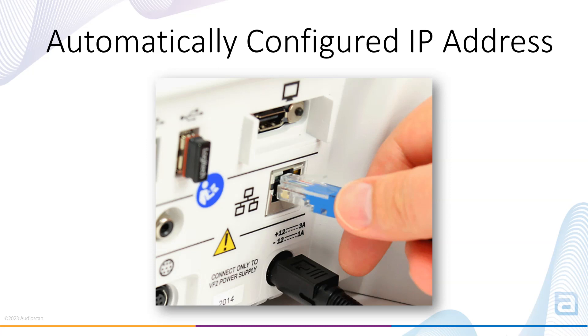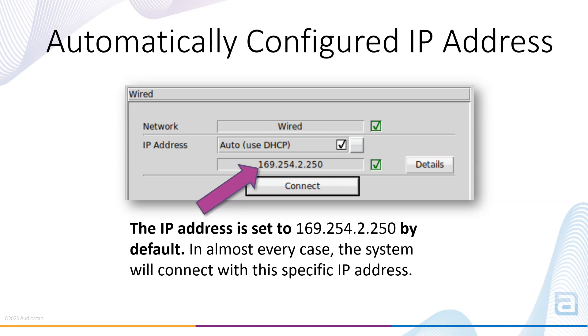For users with a new AudioScan device or a device that is not yet connected to a network, the connection will be established automatically upon connecting an Ethernet cable. For a new Verifit 2 or Axiom, plug in the Ethernet cable to the equipment and the PC and power on the device, or with the AudioScan already powered on, connect the Ethernet to the computer and to the Ethernet jack on the Verifit 2 or Axiom. The IP address will automatically configure. By default, the IP address is 169.254.2.250. Only in very rare instances when the PC has been assigned this exact address will the IP address configure differently.